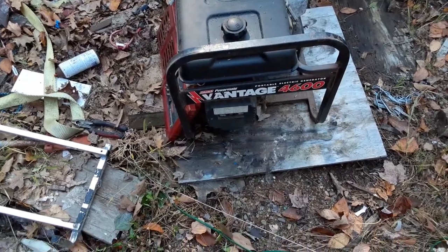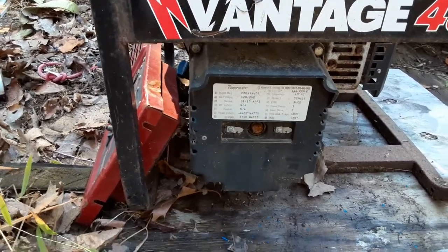Portable generator, or portable electric generator. At least they actually give you the actual physical specs here. Max ambient temperature is 40 degrees Celsius. Duty rated as continuous. RPM 3600, single phase. Current is anywhere between 38 and 19 amps — 19 amps at 220, 38 at 120. It's going to push quite a bit of amps for a little guy. Surge at rated maximum is 5750. Continuous should be about 4600.